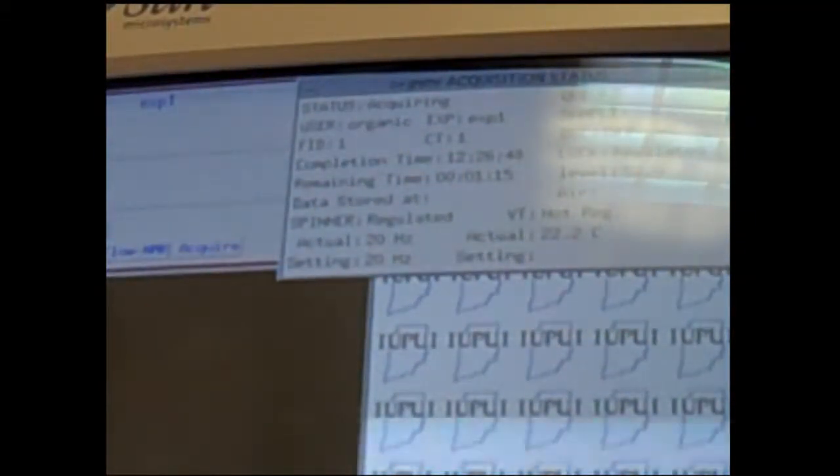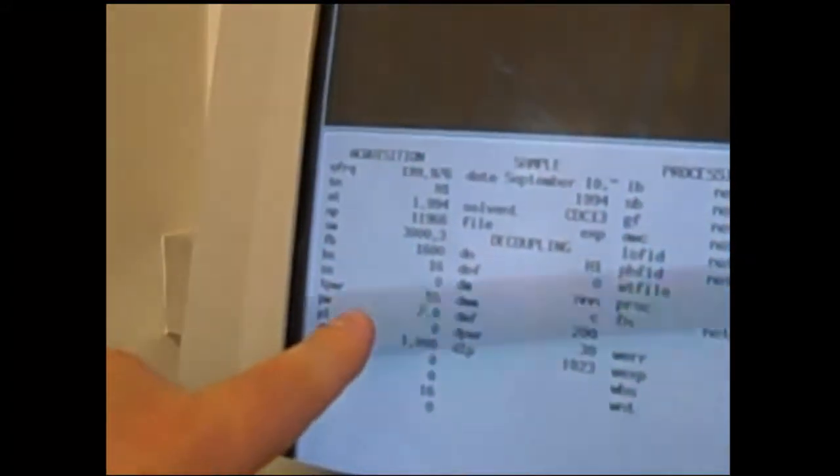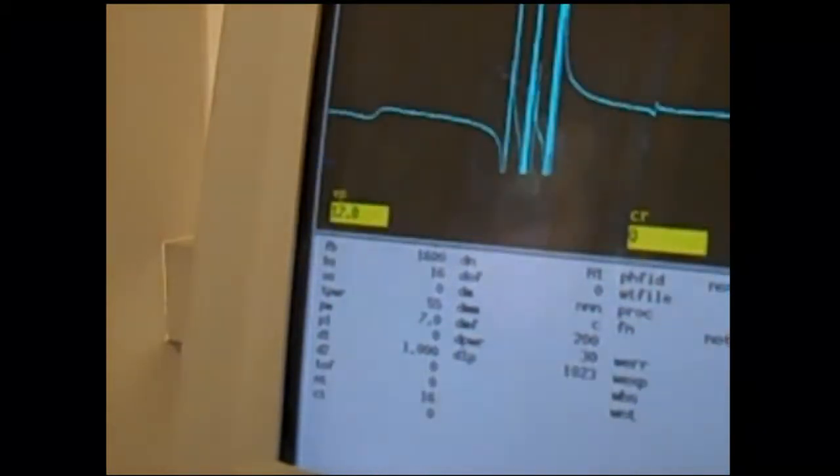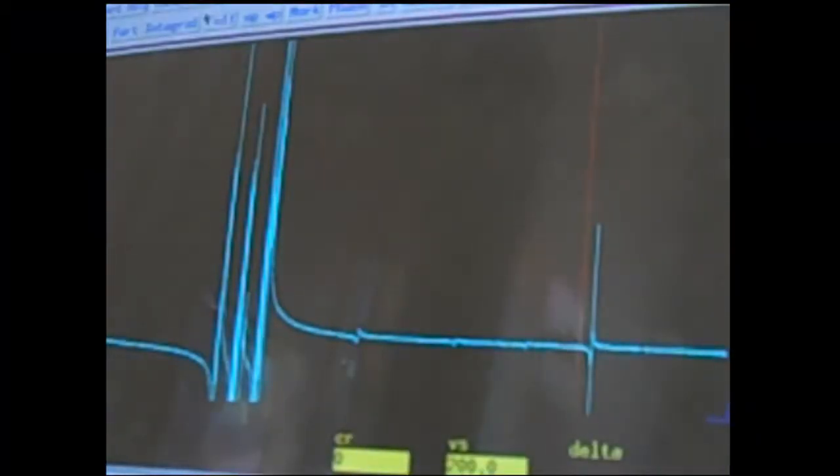The radio frequency scans are starting, and you can actually monitor how many scans are taking place by the CT. That's the count, the number of radio frequency scans that have occurred. A normal H NMR will undergo 16 scans or 16 count. You'll notice it acquiring up to that level. If you notice an error during this time, like gain failure, pulse width driven to zero, you can adjust the pulse width, which is shown right here. Pulse width is 7. You can adjust the pulse width to lower numbers, such as PW equal to, if the sample is too concentrated.